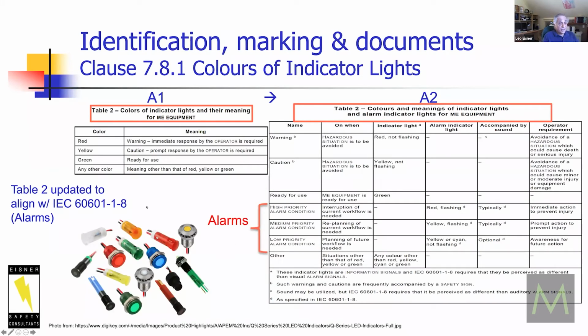This is a big change in the standard, and I recommend anyone that falls under 601, or is pushed into 601, do a big gap assessment of their products against this table. The alarm standard committee put a huge amount of work into it, but that's not the reason to look at it. It's because it's basically forcing anyone with lights or indicators and audio to account for this, since there's an accompanying sound column and an indicator light sound column for flashing lights and indicator lights.